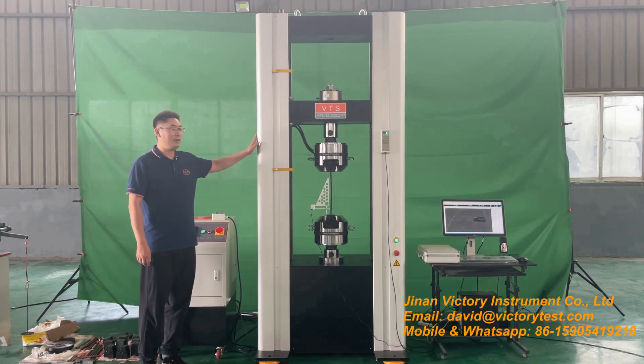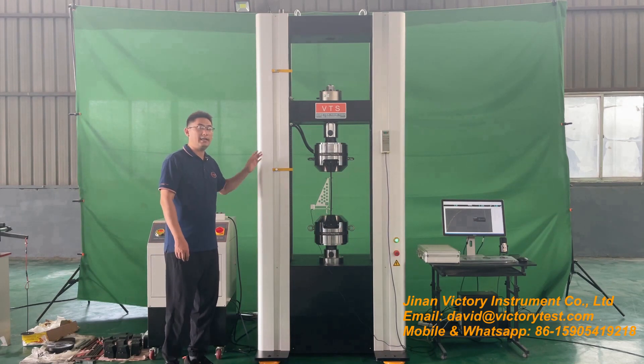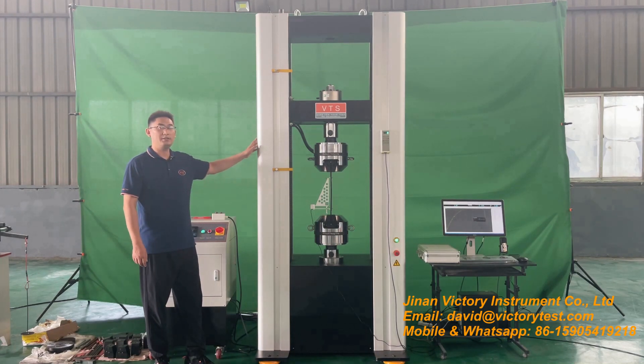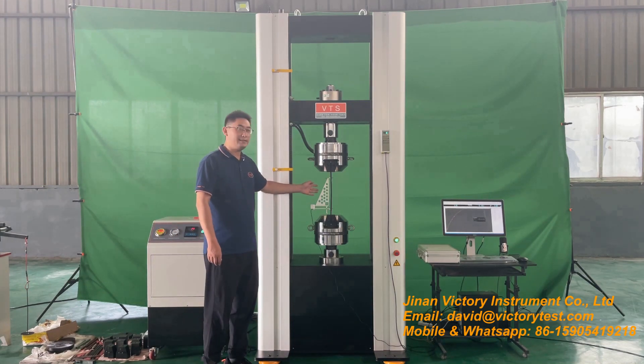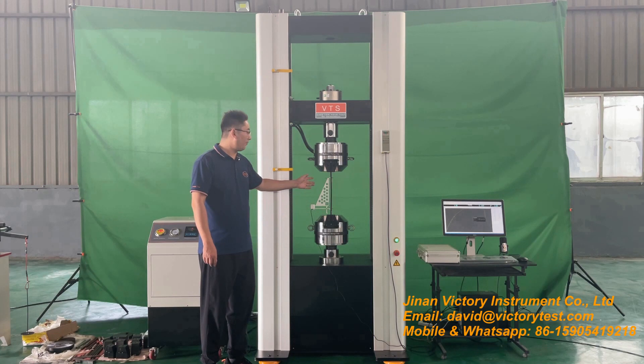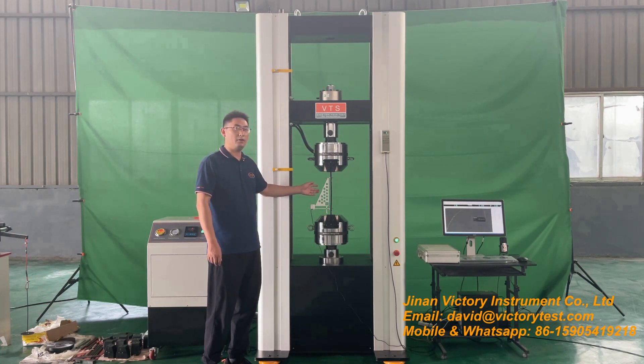The host machine is strongly built. It adopts a large floor standing structure. The net weight of this host machine is 2 tons. It adopts a single test space, and the tensile, compression, and bend tests are performed at the lower test space. It is very convenient for operation.